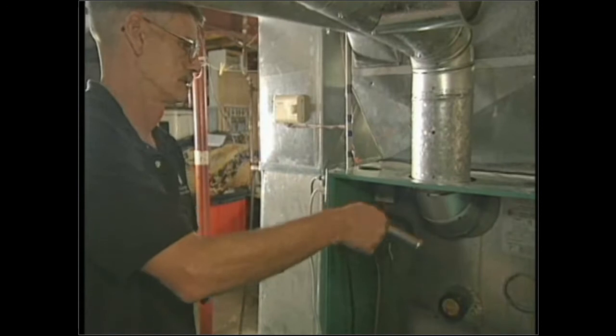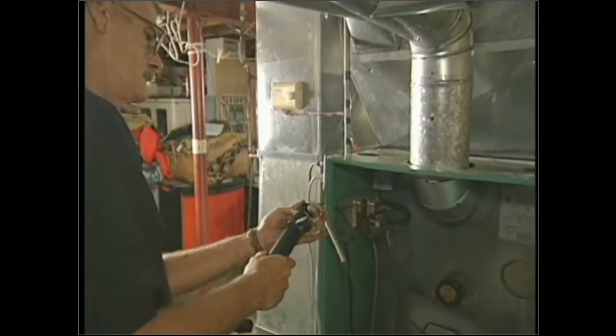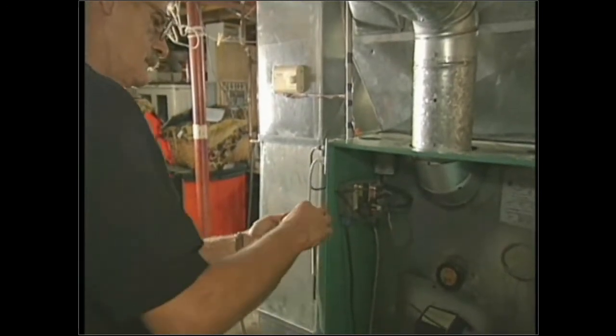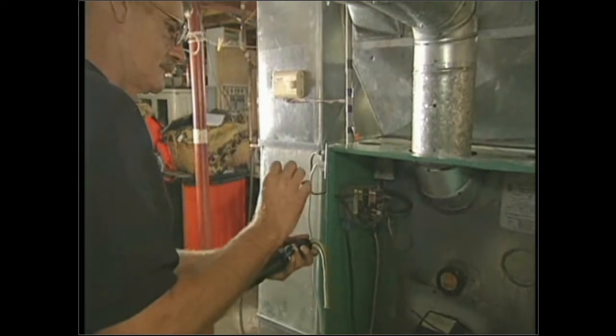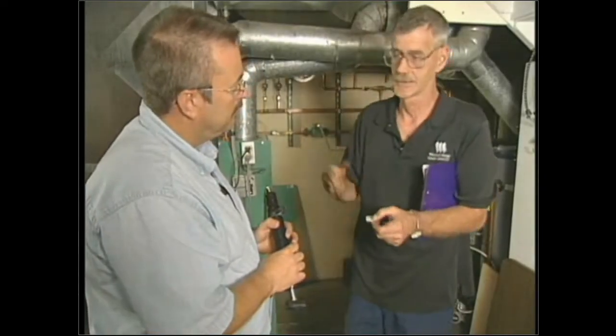Then I'll take that paper out and I compare it to a chart. That will tell me what the amount of smoke is in that unit. We're very fortunate with this one. This one has zero smoke, which is clean and white. Okay? Now, if it had a yellow trace to it, that would mean that there's unburnt fuel, and there's a sign of a problem. Not quite enough to make smoke, but it's unburnt fuel.